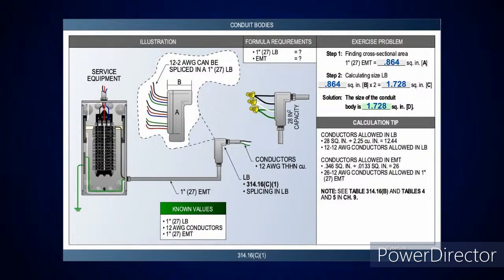How do you know what that cubic inch value is? You take 0.346 square inches and divide it by 0.0133 square inches, and that gives you the conductors allowed — which equals 26. It's showing you, depending on how you set this up based on the tables, that's how you go in and determine the size of the conduit body and the fill required.